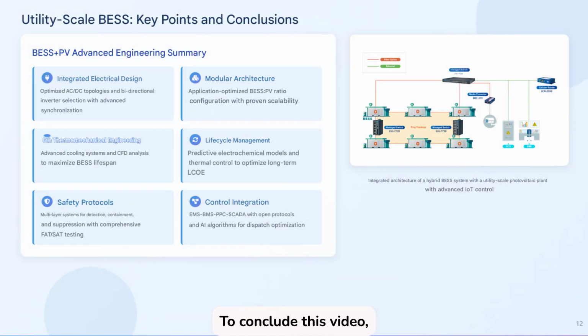To conclude this video, let's summarize the 6 technical pillars we've developed throughout this video. Each of them is essential to ensuring that a hybrid PV plus BESS plant is efficient, safe, profitable, and scalable. Integrated electrical design: selection of optimal AC-DC topologies according to the use case. Bidirectional inverters with fast ramps and grid-forming capabilities. Advanced synchronization with IEC 61850 and OPC UA protocols. A good electrical architecture reduces losses and improves dynamic plant control.